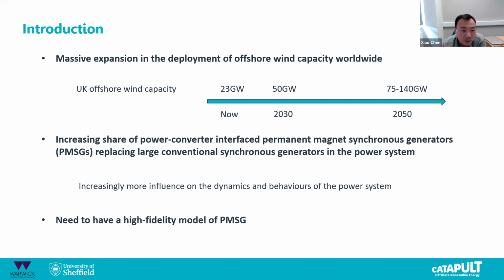So this actually means there's an increasing share of power converter interfaced permanent magnet synchronous generators, which will replace the large conventional synchronous generators in the power system. These permanent magnet synchronous generators are one of the popular topologies for offshore wind turbines. This means they will have increasingly more influence on the dynamics and behavior of our power system. To model those dynamics and behaviors, we need a high fidelity model of our permanent magnet synchronous generators used in hardware in the loop testing.